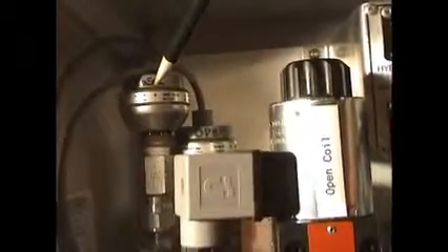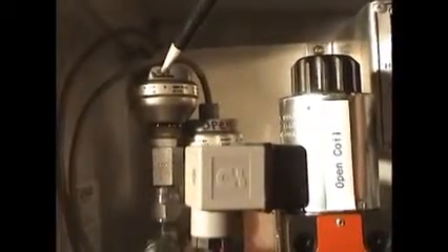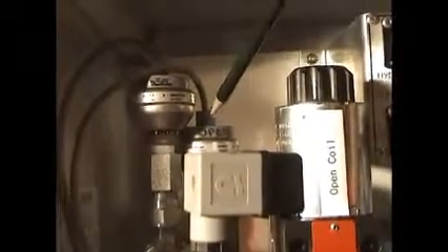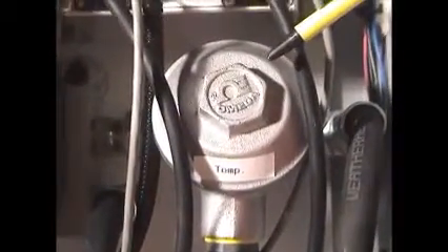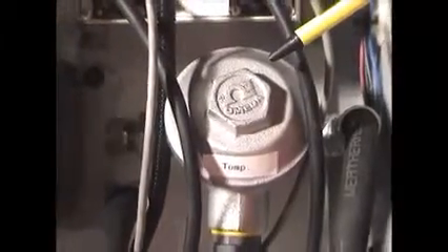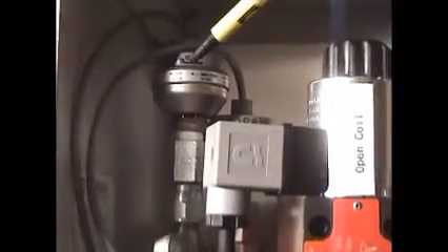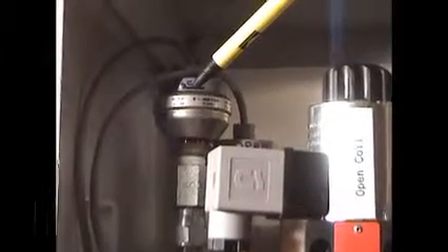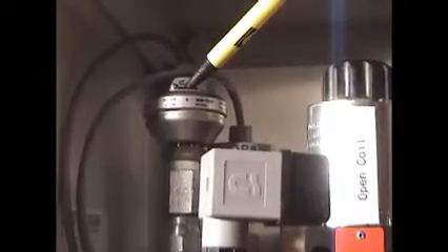2 hydraulic pressure transducers provide feedback to the Dredgemaster system, providing pressure readings during open and closed periods of the hydraulic cylinder. A temperature transducer continually monitors the hydraulic oil temperature, and when a 30-degree temperature fluctuation occurs, it triggers the Dredgemaster to recalibrate the hydraulic cylinder, giving the operator accurate feedback of the hydraulic cylinder's position on the Dredgemaster screen. In the event a hydraulic pressure transducer should fail, easy replacement of the transducer can be performed by removing the wire connection on the panel and loosening the fitting at the base of the pressure transducer.